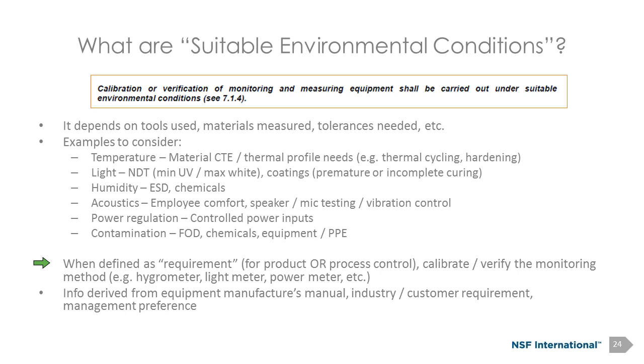If we're not defining a tolerance, we're not defining a value that it has to operate in, calibration may not be required or verification efforts may not be required. But if we're defining an environmental condition or we're defining a requirement associated with a process, we really need to have those tools that are being used to monitor that calibrated or verified. Info derived from the equipment manufacturer's manual may help us to understand what truly does require calibration or verification. The manual is going to tell us it only can operate in a certain temperature range or a humidity range. Therefore, we need to ensure that we're controlling the environment such that it's providing valid results within that range. Something to be cautious about.